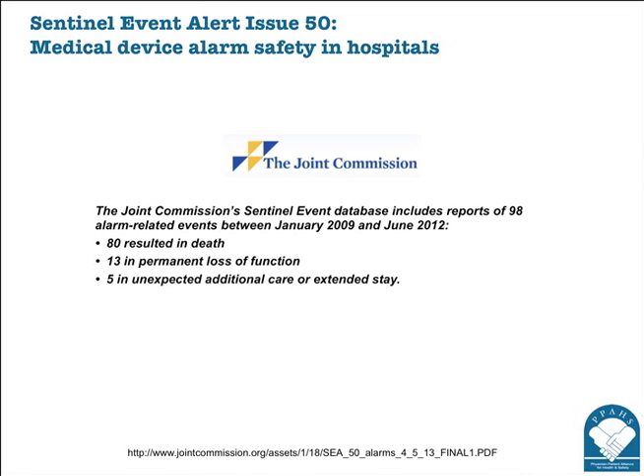In that case, the alarm fatigue that happens is basically nuisance alarms. The devices were not set to alarm for that particular patient; they just set it at its default settings. Patients move, patients scratch, patients pull on things. Whenever any of those things occur, those machines aren't able to detect the condition of the patient, so it's been programmed to alarm. When you have several patients on a floor, all on one device or another with alarms attached, it's just a constant barrage.